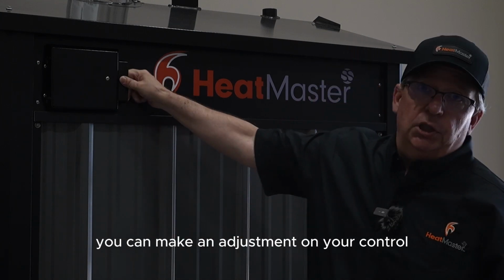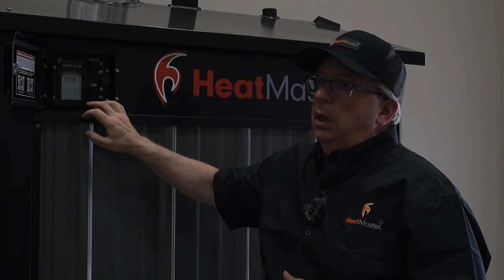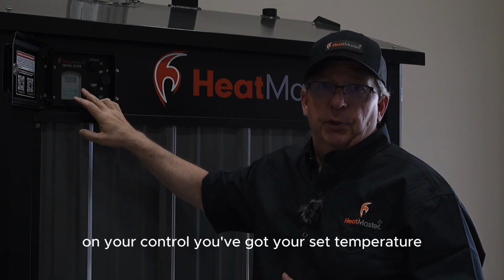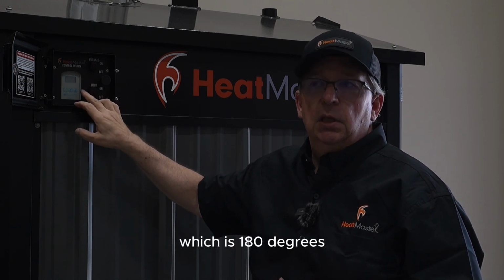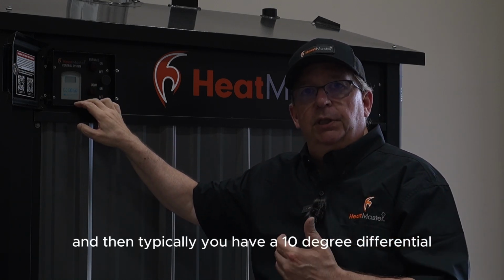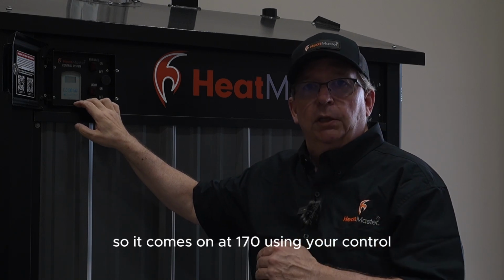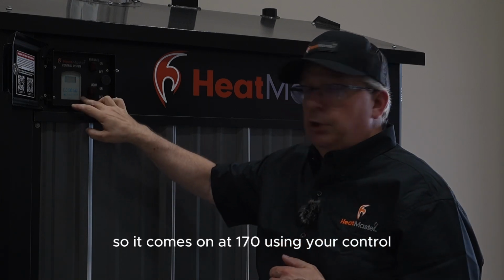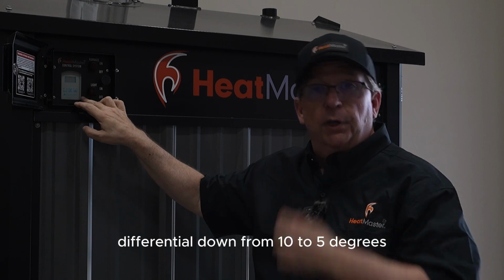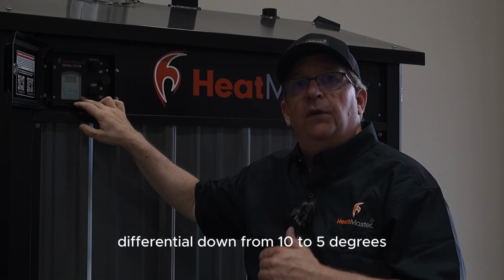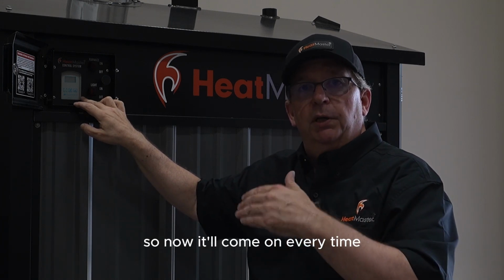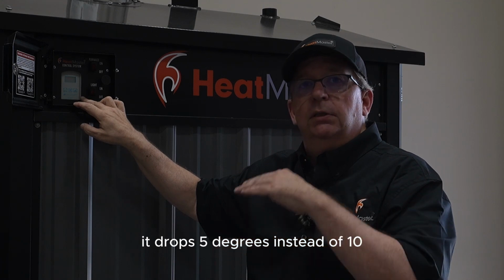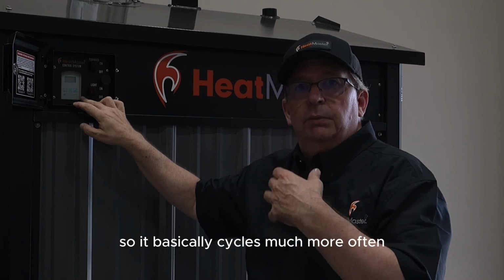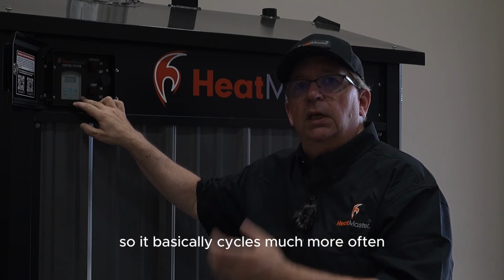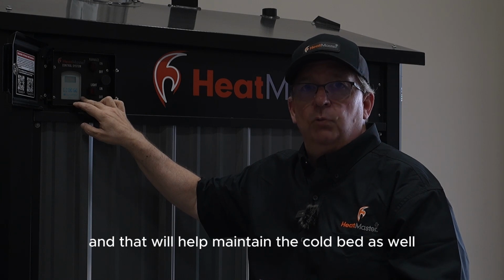Secondly, you can make an adjustment on your control. Now, we talked about it earlier. On your control, you've got your set temperature, which is 180 degrees. And then typically you have a 10-degree differential, so it comes on at 170. Using your control, you can adjust that differential down from 10 to 5 degrees. So now it'll come on every time it drops 5 degrees instead of 10. So it basically cycles much more often, and that will help maintain the coal bed as well.